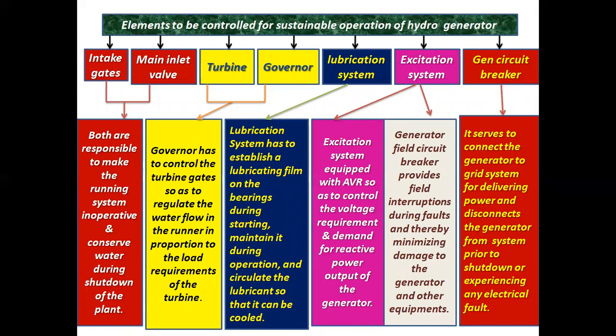Elements to be controlled for sustainable operation of a hydro generator. There are several elements, of which the important ones are: one, intake gates, that is where the water is coming from; main inlet valve; then turbine; governor system; lubrication system; excitation system; generator circuit breaker.